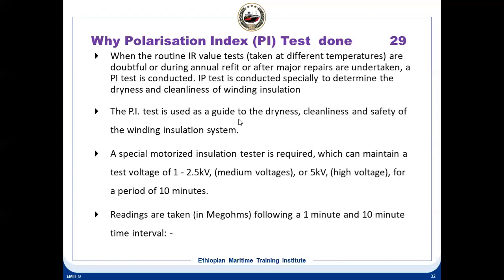And this test is carried out at annual refit time, when major repairs are undertaken, or when the generator is lying idle for a long time. Under these situations, a PI test is carried out. A special motorized insulation tester is required for this, which can maintain a voltage of about 1 to 2.5 kV or 5 kV, 5000 volts, for about 10 minutes. Readings are taken at the 1 minute and 10 minute intervals.